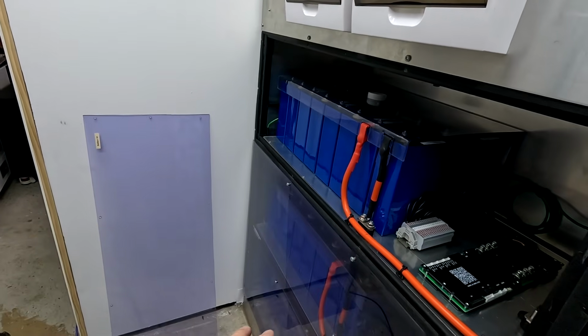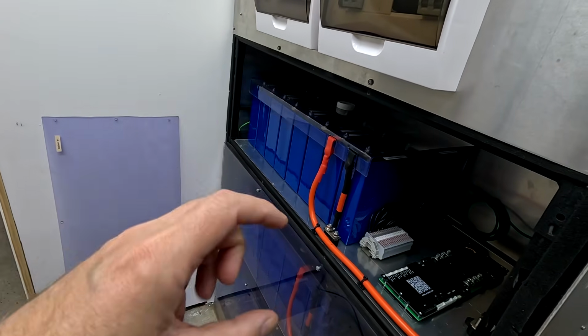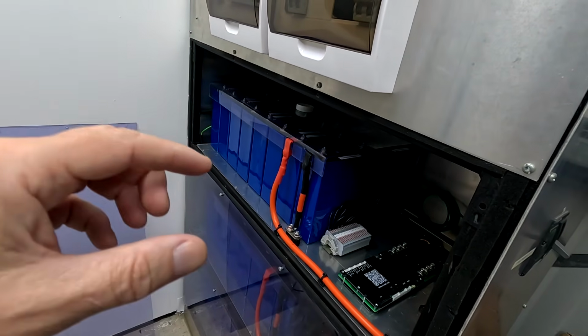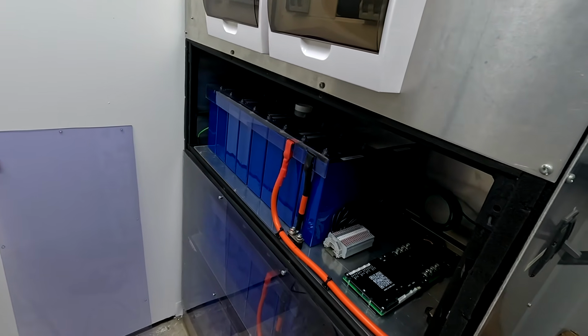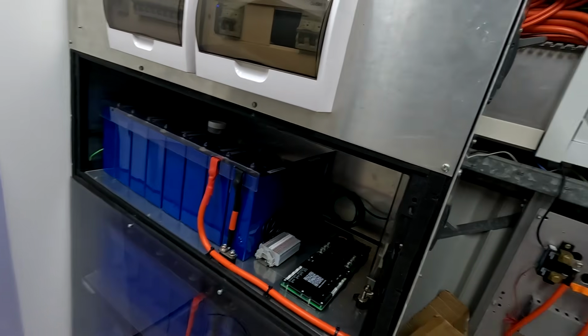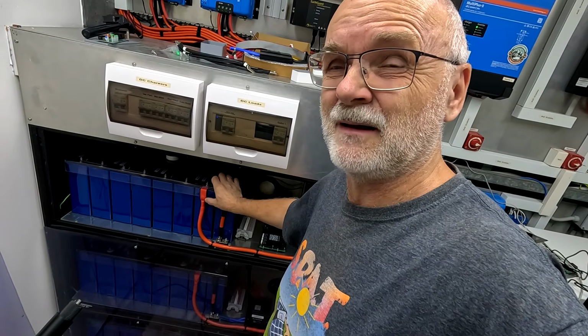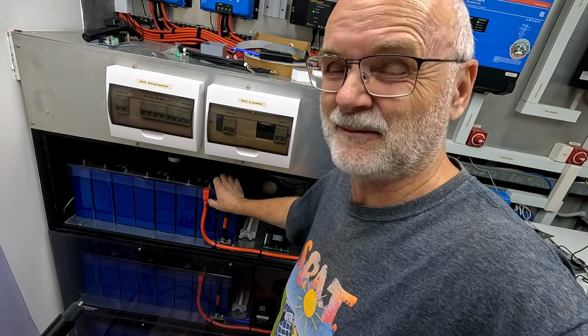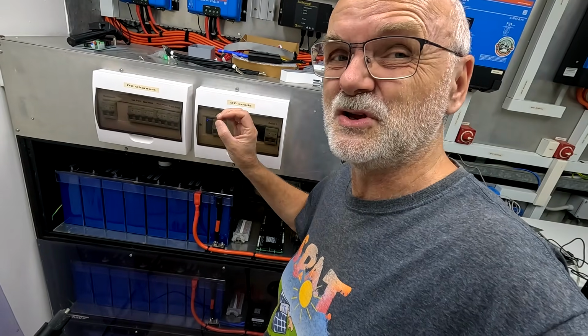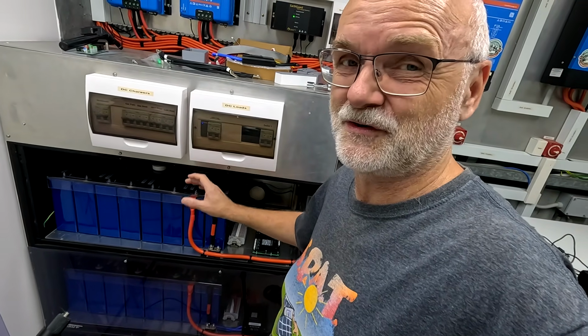So I'm upgrading all these batteries here with fuses with at least 50, 75 or even 100 kiloamps of breaking capacity. I'll probably choose a 200 amp fuse here, or maybe 150 amps, I'm not sure yet, because this would be a pure short current protection.